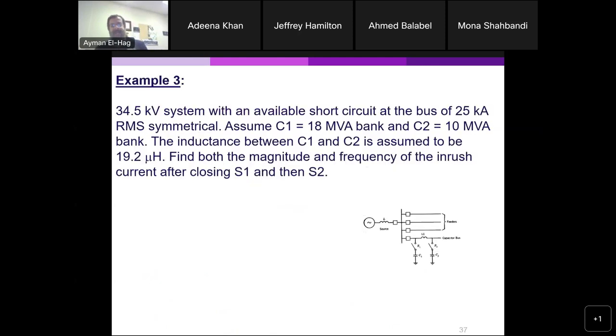So let's have a numerical example so that we have a feeling. The voltage level is 34.5 kV, a very typical primary voltage level in the distribution system. The available short circuit current is 25 kiloamps. What does this mean? If a symmetrical fault happens, the system can provide around 25 kiloamps of current. So having the voltage and the current, we can find this impedance. But this is the only thing that will limit that current.